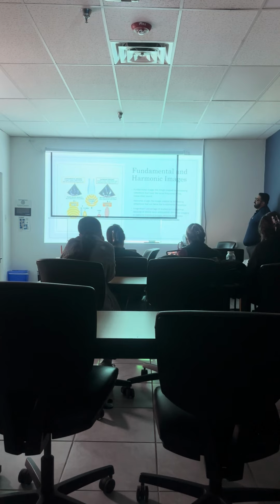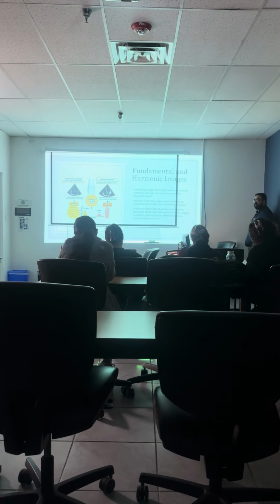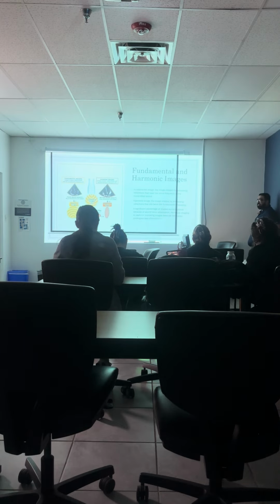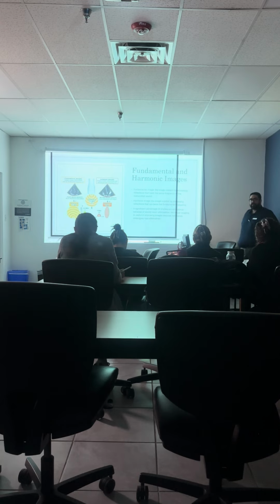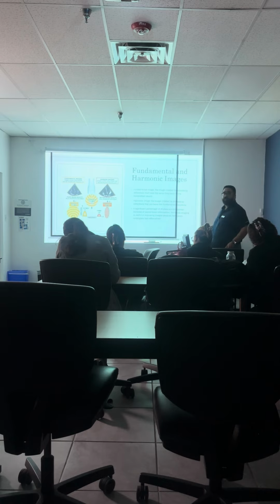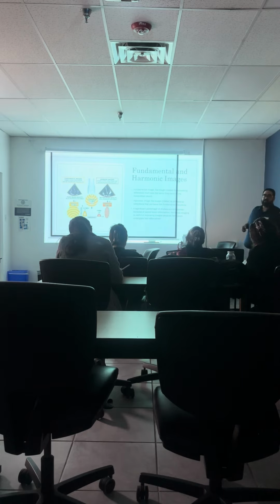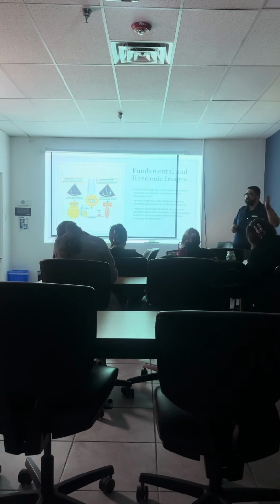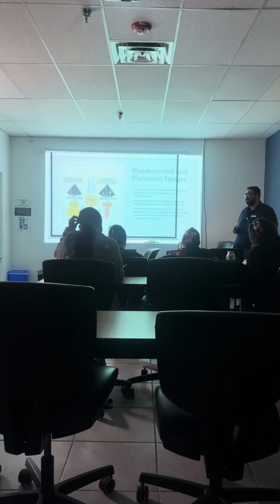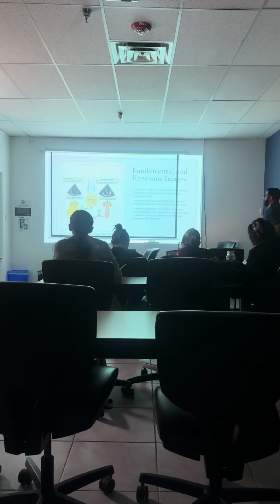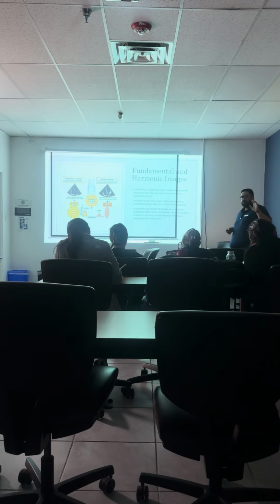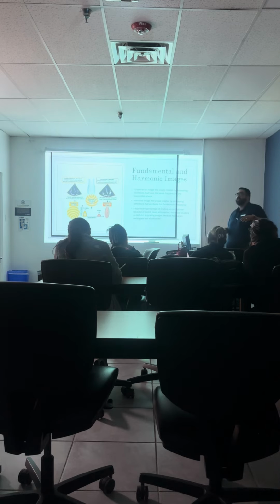All right, so the fundamental image. Fundamental, what are we talking about? Basic. Basic, okay, which means the machine preset, right? What the machine is supposed to be imaging. Okay, so the fundamental image is the image created by processing the reflections that have the same frequency as the transmitted sound. So if we have a 5 megahertz ultrasound machine, it's gonna be focused on the frequencies that are 5 megahertz. Okay, does that make sense to everybody? Yes. All right, now for harmonic imaging, the image is created by processing reflections that are twice the fundamental frequency. So if our ultrasound machine is at 5 megahertz, what's the frequency of the harmonics? 10. It's 10, okay, just twice.